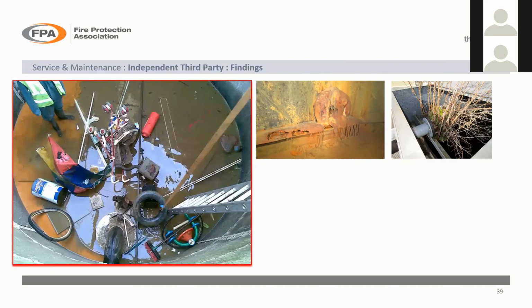This is a picture that's been provided to me. This is the kind of thing that people put into your tank if you don't address the security of your tank. If you look at that, it is a requirement that you check the ball valve on your tank on a weekly basis, and on a monthly basis, the security of it. You can see all kinds of things have been dropped in there.